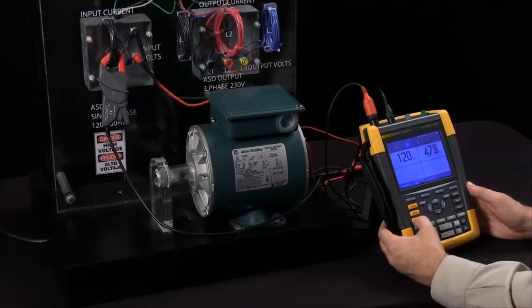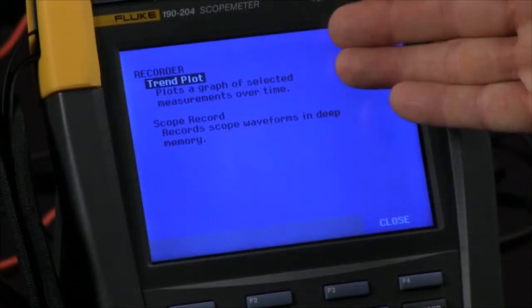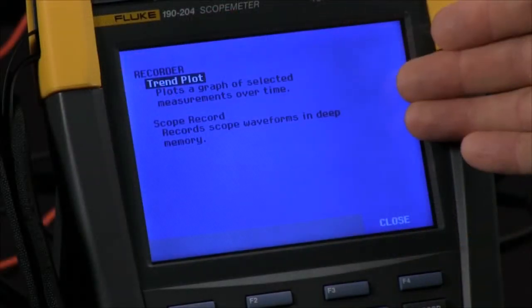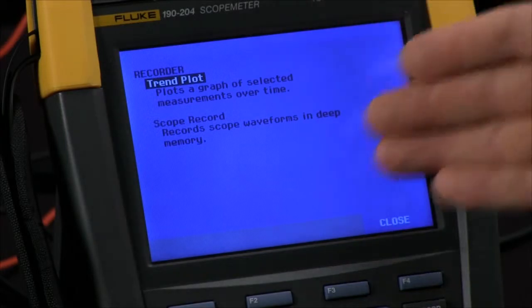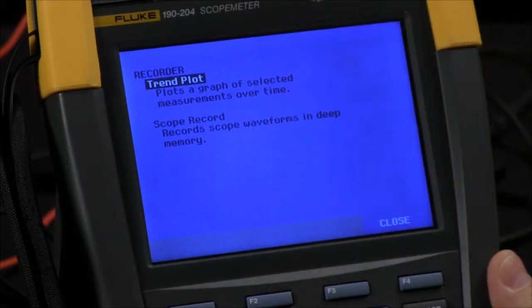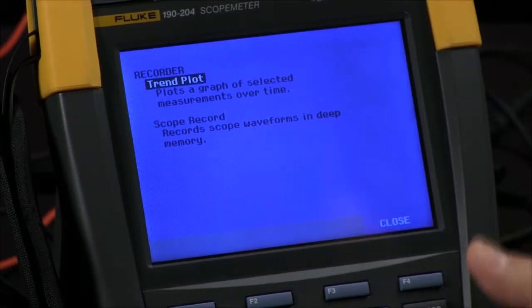Another option: when you go to your recorder selection we can either do a trend plot which is going to give us an RMS graph of my signals coming in. We can also go into scope record which is going to save the actual waveform in deep memory.